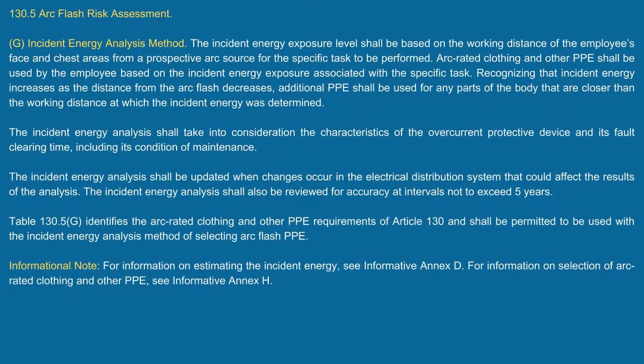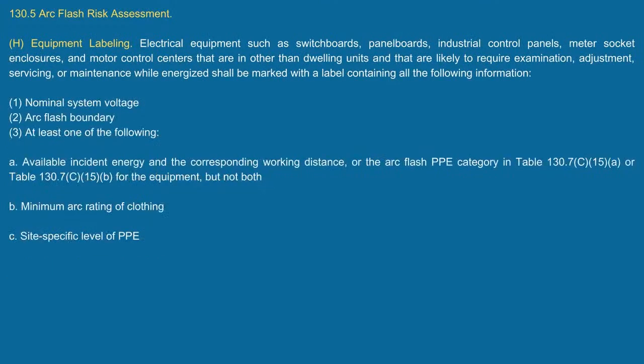And then the next one after that says, when you're selecting and identifying your arc-rated clothing and other PPE requirements, look what table it tells you to go to. Table 130.5G when you're doing the calculation method. Okay? Right. Now, after I get through that, then you look at the equipment labeling.